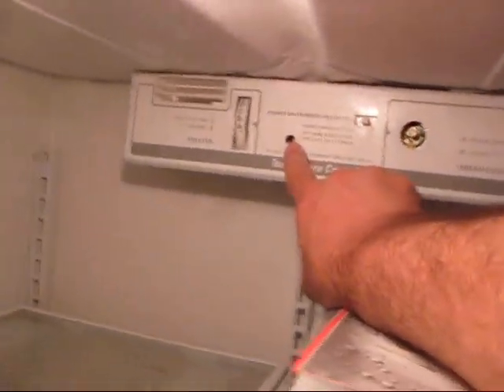The defrost timer has settings. There's a plug, and inside there's a place to stick a screwdriver that cycles the defrost timer. If it's in defrost and you don't want it in defrost, you can stick your screwdriver in there — it only turns one way. You can hear it clicking and it'll come on. The way it defrosts is it's got a heating element in there that looks like an oven bake element on the coil. It warms up and melts the ice. There's a little thermostat that senses if the coil is too hot before letting the compressor come on, because sending hot refrigerant into the compressor is bad. You can click it out of defrost.